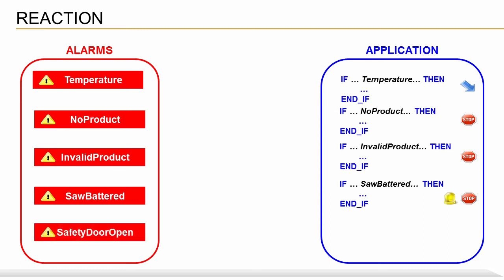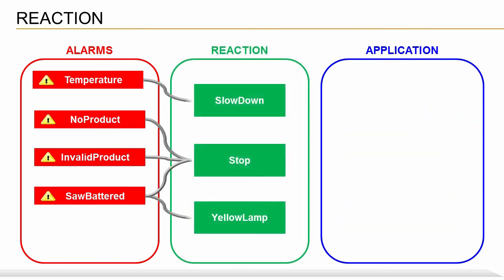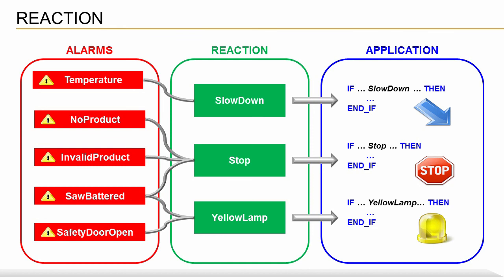In this situation, any time you create a new alarm, you also have to adapt the control application accordingly. By using reactions, on the other hand, each alarm can simply be assigned the appropriate reaction. In our example, we have defined three reactions: Slow down, stop, and yellow lamp. Each of these reactions is implemented in the control application. Now, if you add a new alarm, all you have to do is assign it to an existing reaction. There's no need to adapt or expand the control logic.